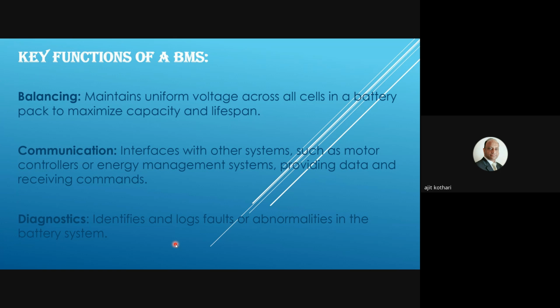Another important function is communication. Communication is very important to give the information of the battery bank to the external world, let's say by CAN, IoT, or RS485 - communication ports are available. So however you want the information given to the external world, or to monitoring devices, or the display unit where this information has to be displayed, that information is given to that device from the BMS.